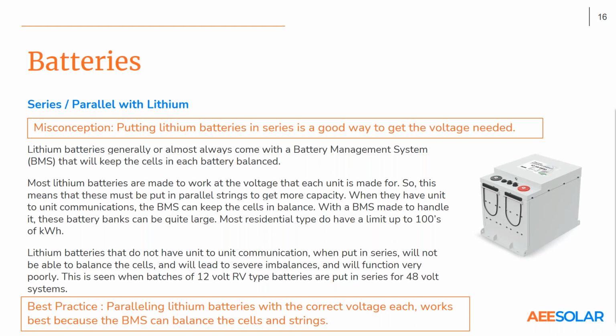But the balancing in these batteries mostly happens when they are fully charged. So to really get them balanced, you have to bring them up to a really full state of charge every so often, every few weeks or so. It's not nearly as critical as with a lead battery, but it really does work better — if you run them between like 10% and 20-30% long enough, eventually they'll become imbalanced, and they really do like to have a full charge held for a little while.